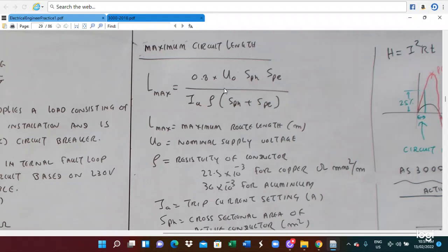This maximum circuit length depends on several factors. They include the supply voltage, the conductor cross-sectional area, and also the protective conductor cross-sectional area. In the meantime, you have to set up the trip current. Trip current is how much current setting you have to utilize at the circuit breaker, the peak current setting, and also the resistivity of the conductor. Those factors determine the maximum circuit length.